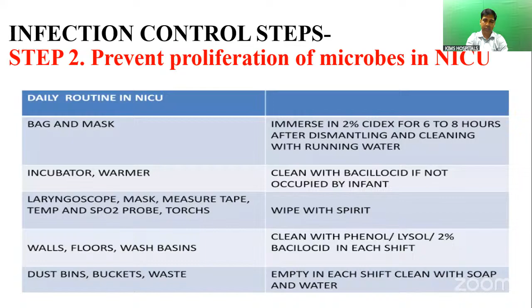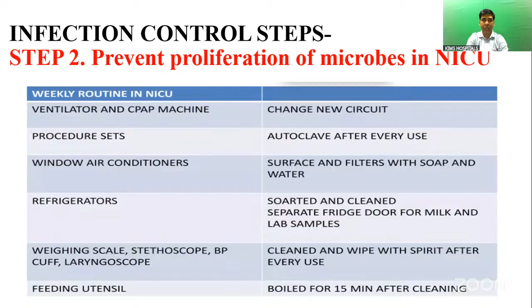Other things are the weekly routine. The ventilator and CPAP machine circuit should be changed weekly. The procedure sets should be autoclaved after every use. The window air conditioner surface and filter should be cleaned with soap and water. Refrigerators should be defrosted and cleaned, with a separate fridge door for the milk and the lab samples. The weighing scale, stethoscope, BP cuffs and laryngoscope should be cleaned and wiped with spirit after every use. And the feeding utensils should be cleaned weekly.